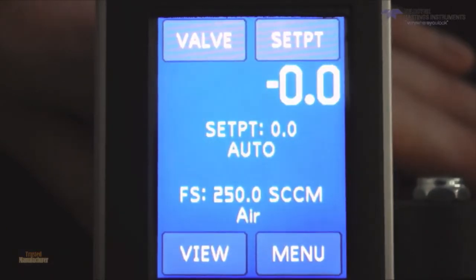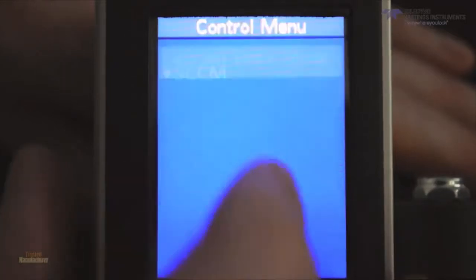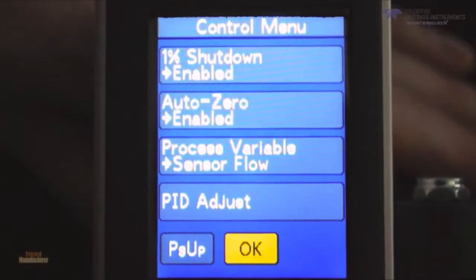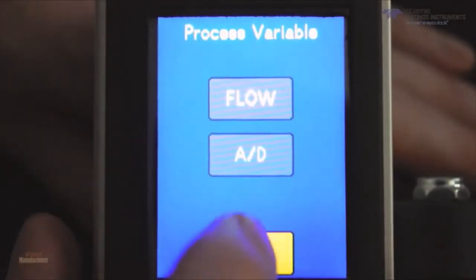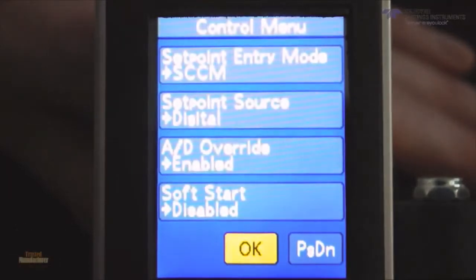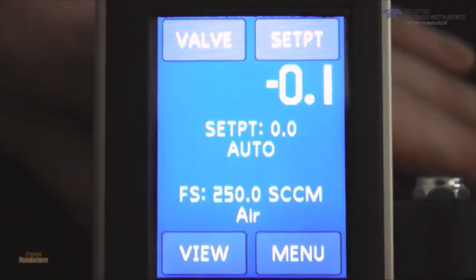First, I'm going to tell the instrument that I want to use the external input pin. This leads to an A to D converter in the 300 view. So to do this, I'm going to go to Menu, and then Flow Control. Go page down, and I'm going to change the process variable from the flow sensor to that A to D, which is connected to pin 1 on the D connector, which we showed earlier.